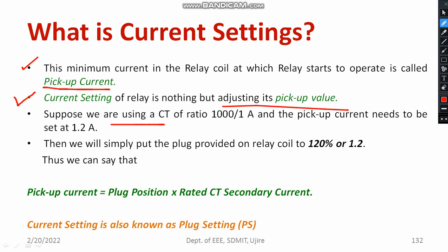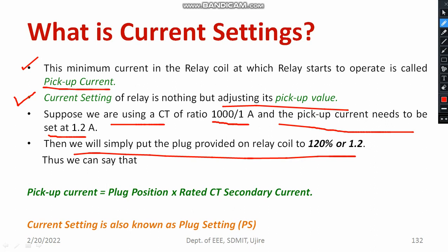Suppose we are using a CT. Why are we using a CT? Because a normal ammeter cannot measure high current, so using the CT you can measure the current. For example, we are using a current transformer in the ratio of 1000A to 1A. The pickup current needs to be set as 1.2A. You can set the pickup value as 1.2A, or simply put the plug to 120%, which you can also call 1.2 — anything is fine. You can express it in terms of percentage as well. The pickup current is plug position multiplied by rated CT secondary current.